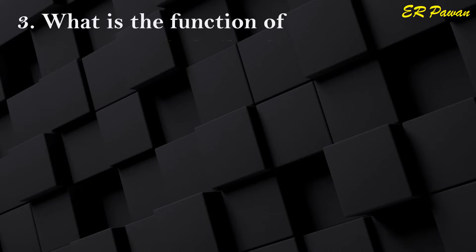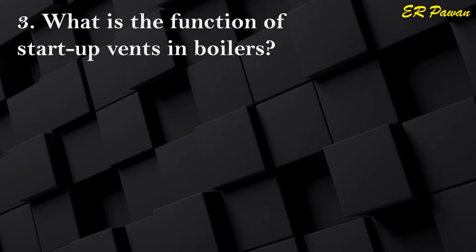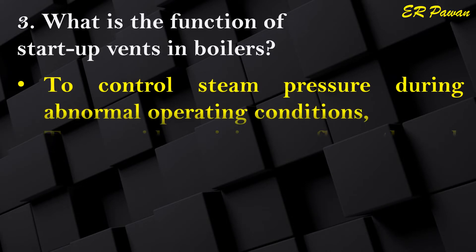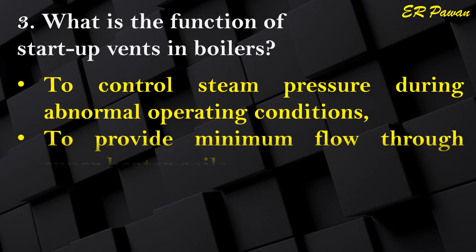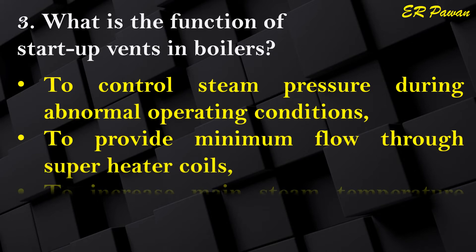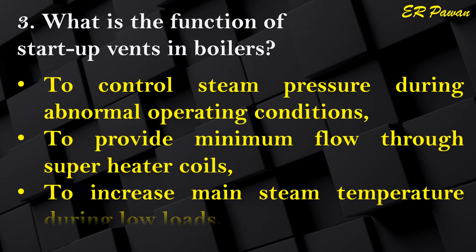Question 3: What is the function of startup vents in boilers? To control steam pressure during abnormal operating conditions, to provide minimum flow through superheater coils, and to increase main steam temperature during low loads.